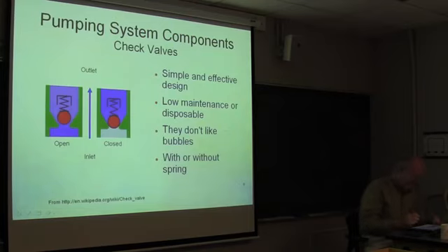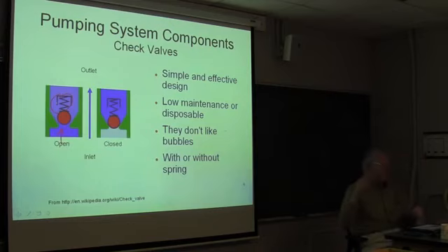Well, hang on one more second. This explains how the check valve works in a little more detail. In the open position, the pressure is pushing the check valve up against the spring. And in the closed position, when the stroke is going the other way, the spring is pushing the check valve down so that we can't have any flow in back of the check valve.